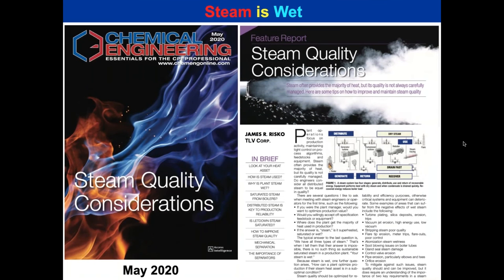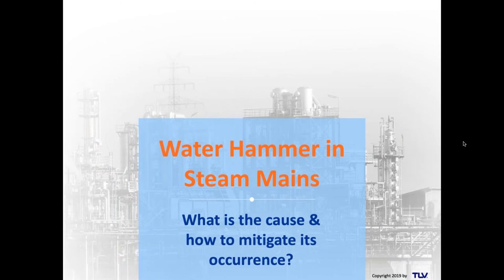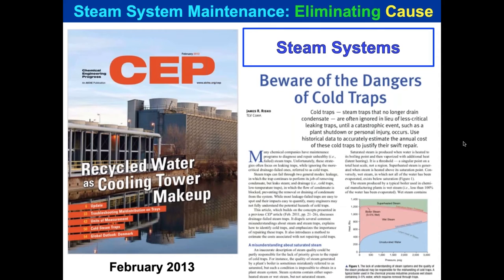If you want to read more about that, there's an article I wrote in Chemical Engineering in May on steam quality considerations — it's on our website. From prior water hammer sessions, we talked about water hammer in steam mains and its causes. Water hammer in steam mains is mostly caused by cold traps that don't drain. I also wrote an article in Chemical Engineering Progress in 2013 about the dangers of cold traps.